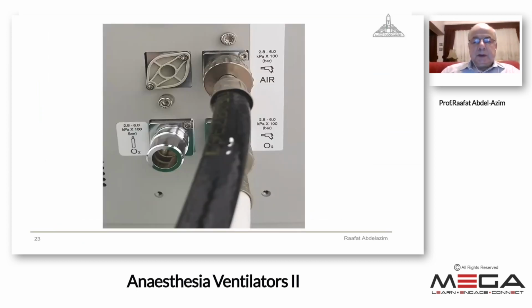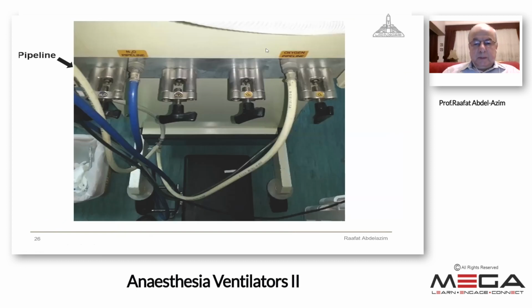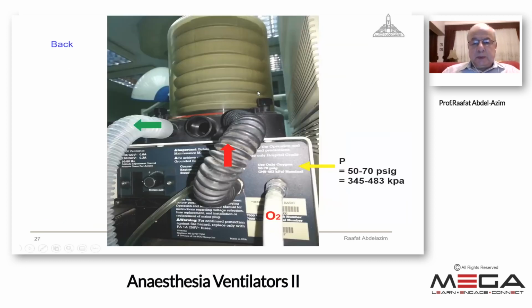In each machine, the operating pressure will be written there. This one is important to understand. Oxygen is coming under 4 bar pressure, going inside the ventilator. This is the back or the rear view of the ventilator. The control panel will be supplied by oxygen under pressure of 4. Then it will be operated, and I will adjust the parameters of ventilation.